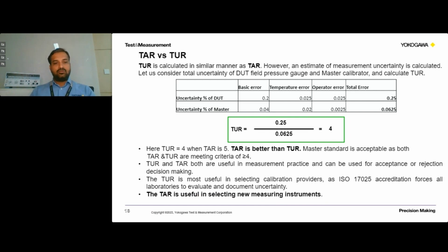And test accuracy ratio is most useful in selecting the new measuring instrument. So whenever we go for purchasing, whenever we go for selecting the standard for our lab or for our industry or for our company, we will check the specifications from the manufacturer, and there we compare the test accuracy ratio. So it is most useful in selecting the new measuring instruments.